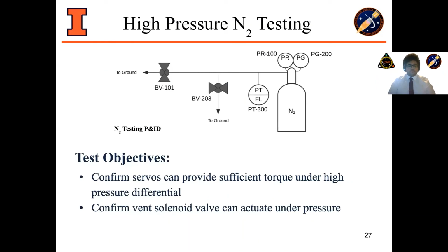Before cold flow and hot fire testing, the calibration of the pressure transducers and the verification of the main ball valve actuation must be completed. The high pressure N2 testing allows us to build that calibration curve by slowly pressurizing the line and noting the values of a pressure gauge and the signal from the pressure transducers for a series of values. This test also allows us to test the actuation of the main ball valve.